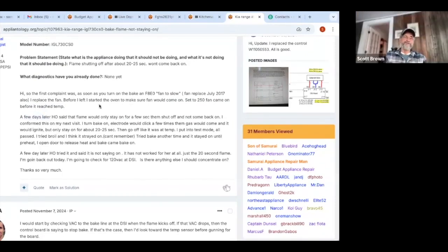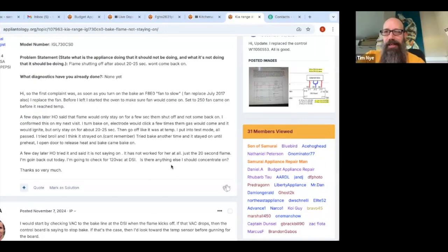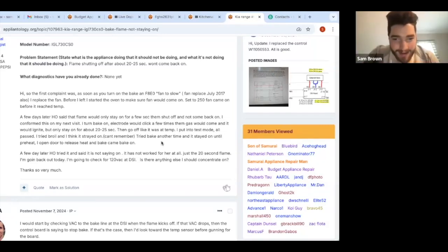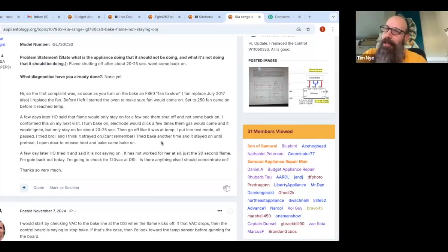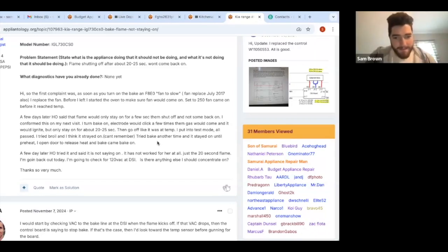Interesting. He never let it get too hot though, because it was set to 250, and the fan came on before it reached temp, so it never got to 250. But presumably it probably ran longer than the 20 to 25 seconds he writes in here. So something changed between it being set at 250 with the fan coming on before reaching temp, and now it's only turning on for 20 to 25 seconds.